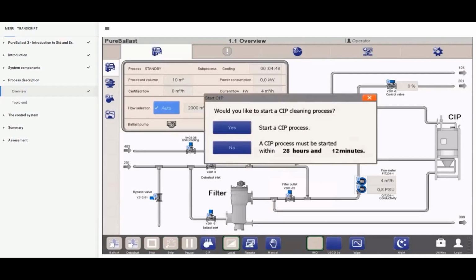A pop-up will appear, asking you if you want to run a CIP cleaning process. A CIP cleaning process must be finished within the time stated in the pop-up. If no CIP cleaning is performed within the time limit, a warning is given. Operations after that will not be compliant. If a new process will be run within the time limit, press No. If not, press Yes to start CIP cleaning.